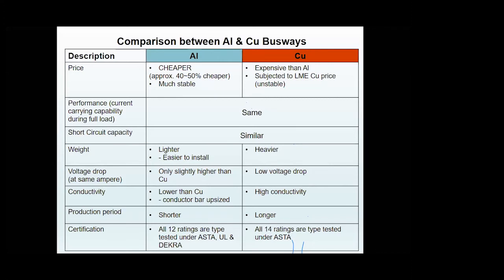The short circuit capacity of aluminum and copper busway are almost similar. Aluminum has another advantage in weight — it's a lighter material, making it easier to handle and install on site. Voltage drop for aluminum is only slightly higher than copper. Lead time for aluminum is shorter than for copper busway. In terms of certification, both our aluminum and copper busway are type-tested and certified by third parties.